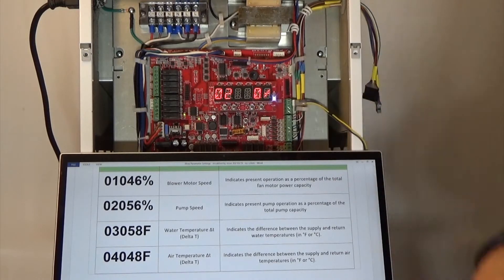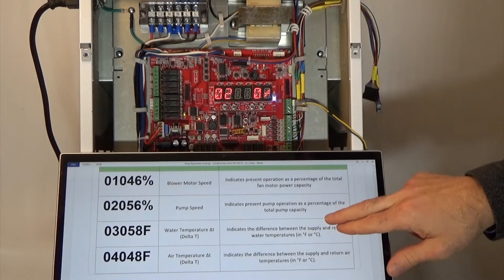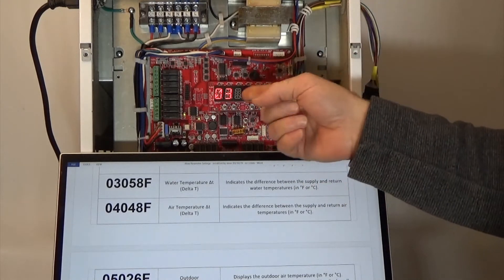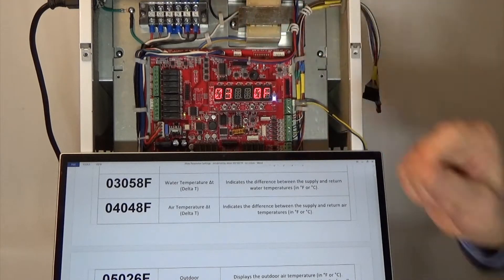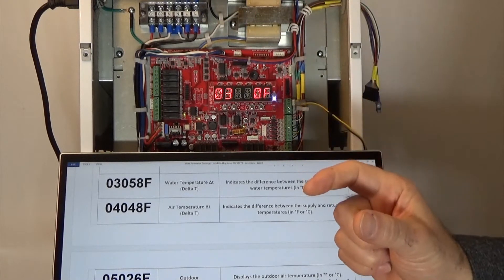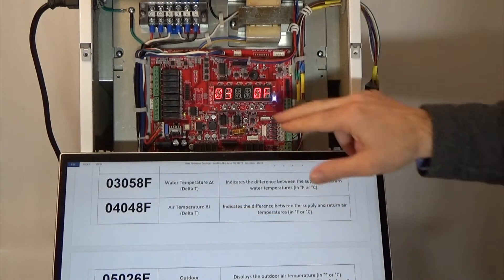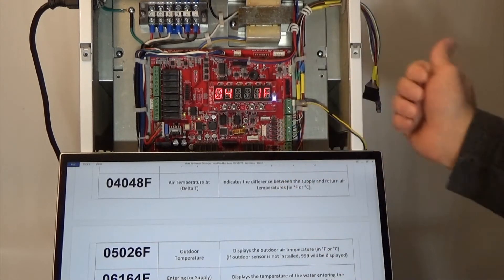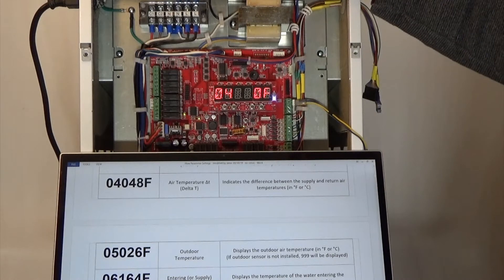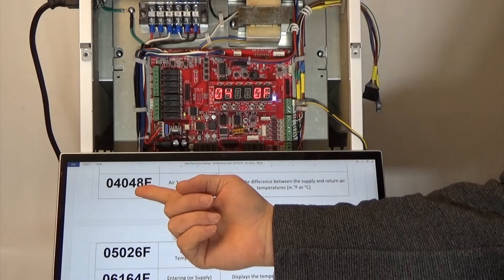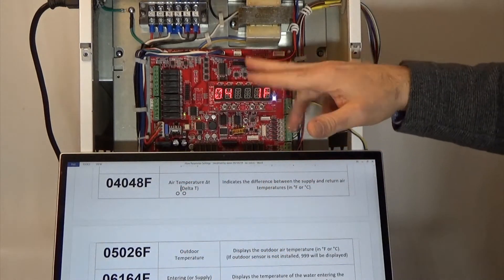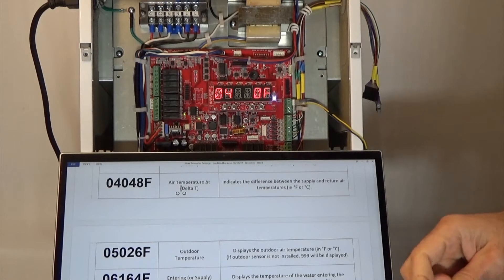This will display 20%, 40%, 80%, depending on what we're supplying to the pump. Parameter number three is the water temperature delta T — we're looking at the incoming water temperature versus the outgoing water temperature and measuring the difference. Parameter number four is the difference on the air side. We look at the return air sensor and the supply air temperature sensor, take the differential, and list it here. This parameter is the difference in air temperatures — return versus supply.